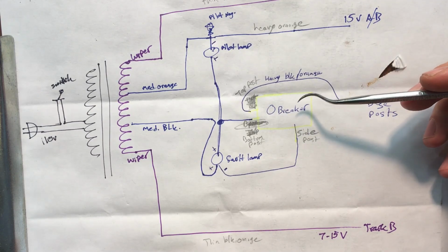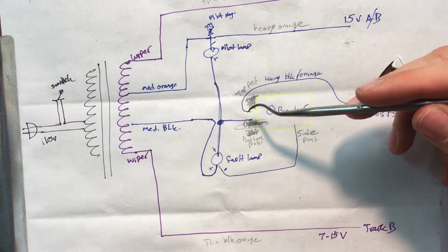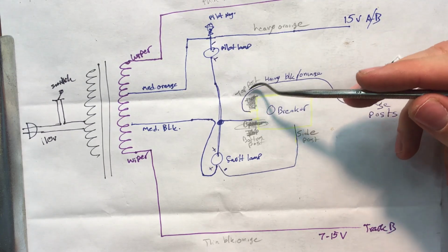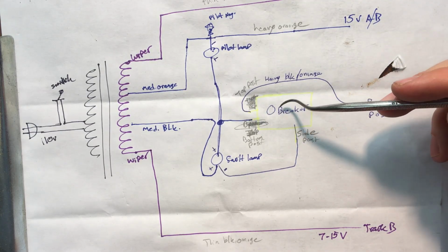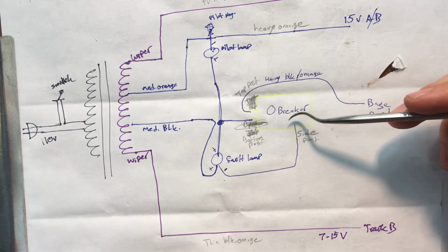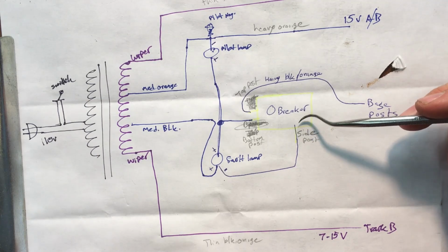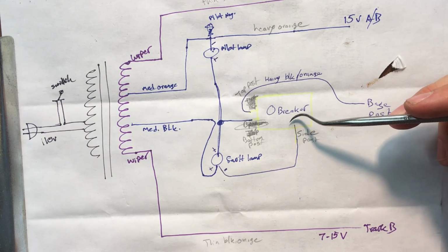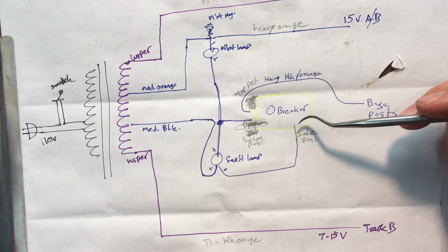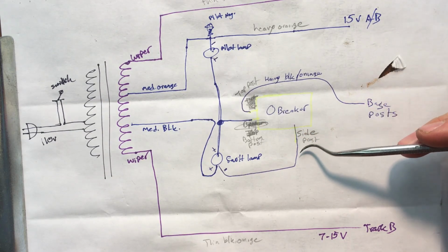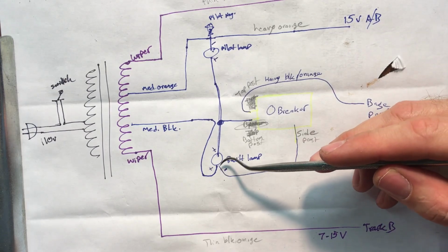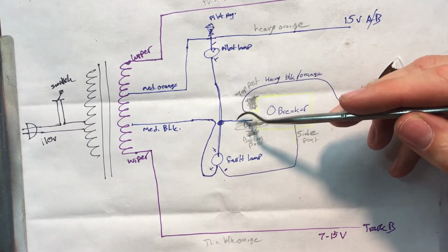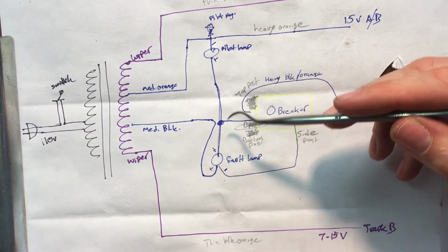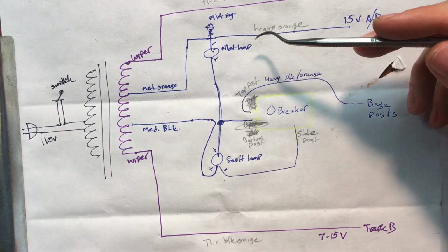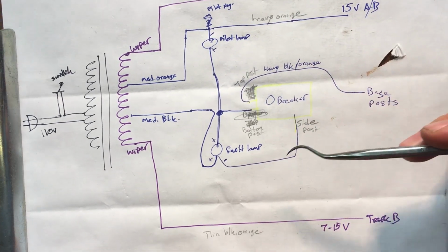Now, if the circuit breaker trips, this is opened, so the circuit to the track is not completed anymore, and the connection to the side post is tied instead. There's a third post on the side of the breaker. If the circuit breaker is open, the power goes instead through the side post, and then that feeds back into the fault lamp. But this portion here isn't connected, so the fault lamp lights and the pilot lamp goes out, as well as all the track power.